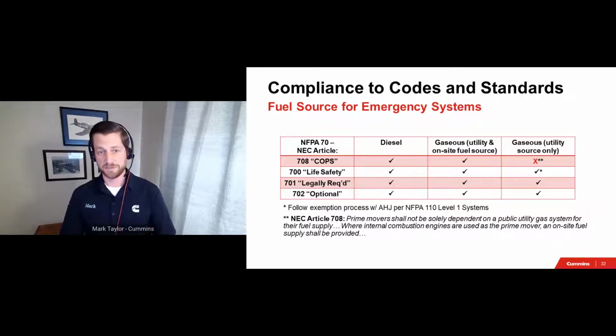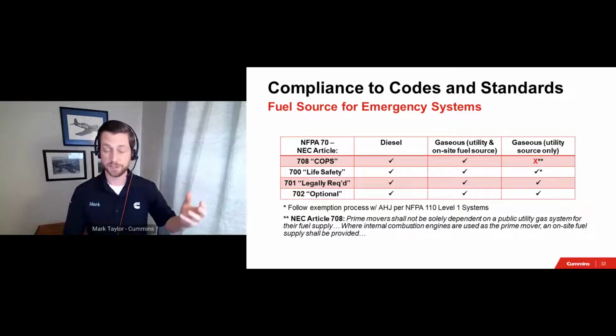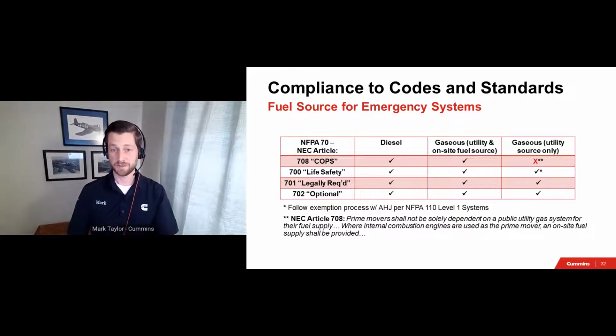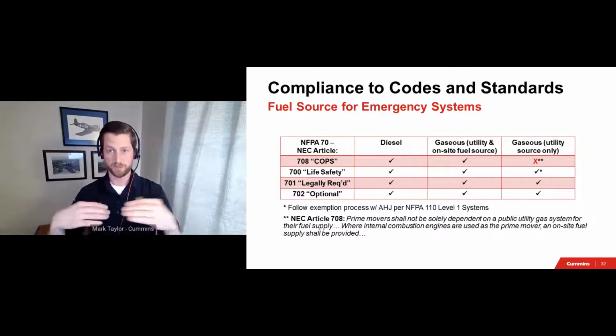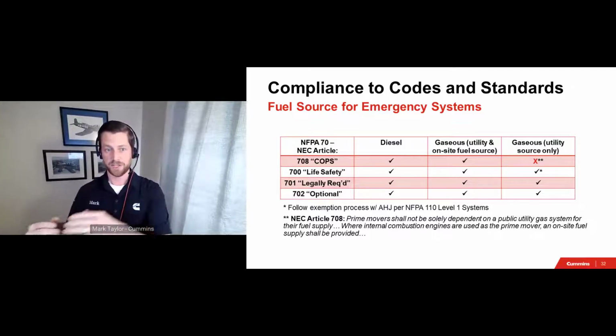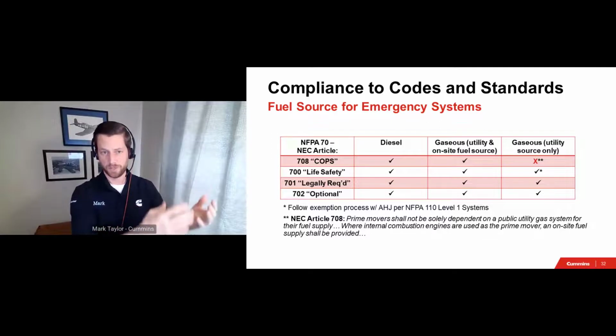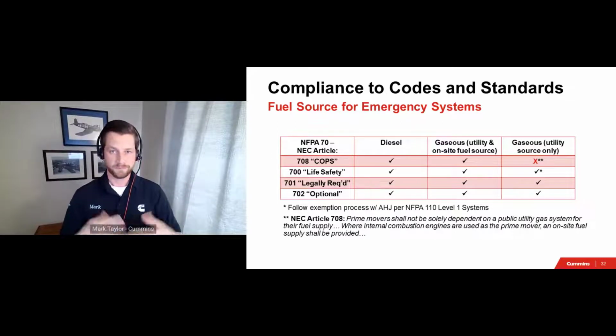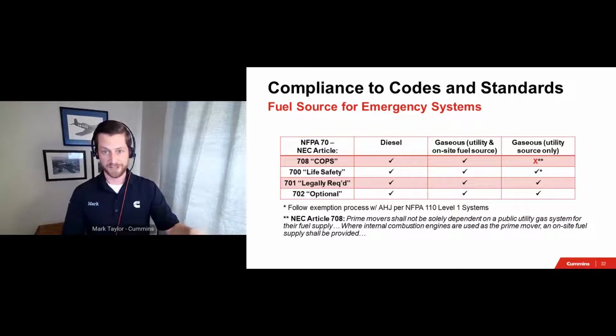But to best summarize gaseous fuel generator sets with utility-only sources of fuel, NFPA 110 Level 1 systems must include on-site fuel storage, again, if the likelihood of the loss of the utility is high. Therefore, once again, I recommend that this drives a conversation with your local AHJ and local utility for what is that definition of high. I must also note, I'm making a general assumption here between Article 700, generally falling in line with NFPA 110 Level 1. Confirm that with your AHJ if there's ever any doubt.